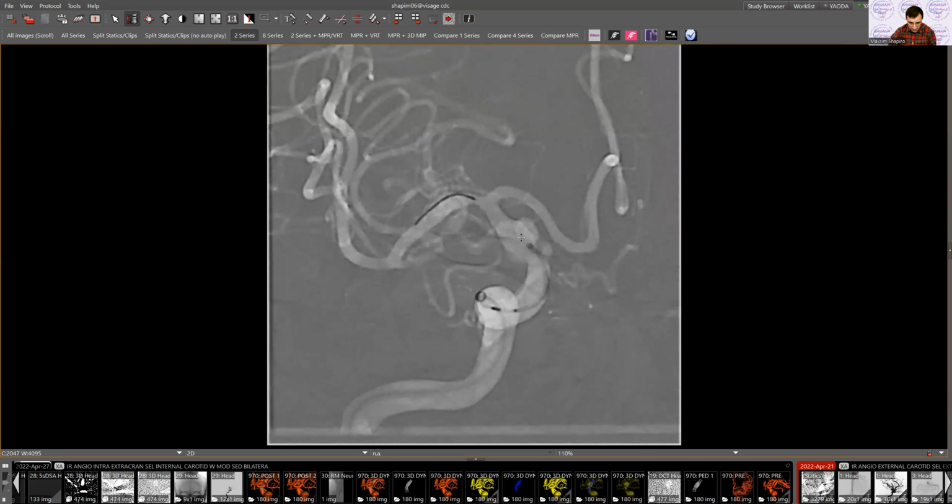There we go. Now we're pushing a little bit of forward load. You see how it opens in this segment. That's what we really want. We want to maximize the coverage here. Now you'll see if you play around with these devices, if you were to compress any of these pipes like this, it's a Pipeline Shield, if you compress it like this, what you'll notice is that your coverage will approach 100%. The more you compress, the more the interstices are going to collapse and you're going to end up with very, very high coverage.